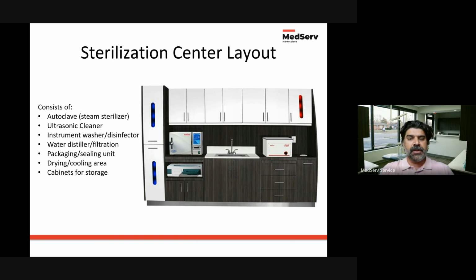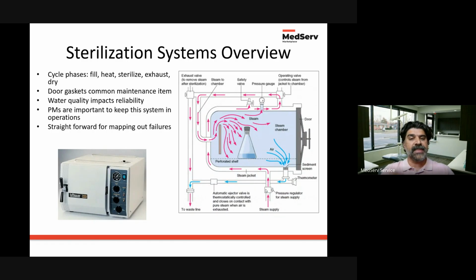Some of the common issues here, you may have already seen on some of the larger equipment you've worked on, have to do with components. The door gasket is a frequent one for the autoclave. If it isn't able to hold the pressure right, it's not going to be operating at its full capacity. There are also drainage or fill faults. Sometimes the plumbing or the water flow is not proper, there's a kink in the tube or a clog somewhere, so that has to be investigated. A lot of the issues in the sterilization center have to do with improper PM execution. As long as these systems are checked regularly, tested, and validated, and all the different components work properly, it's easy to see why things fail when they do.